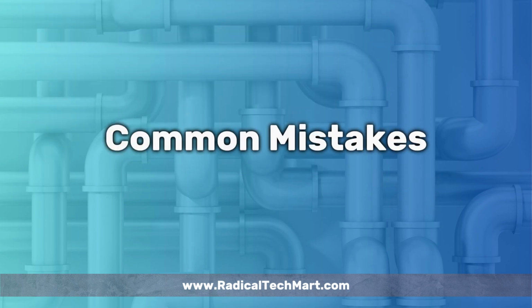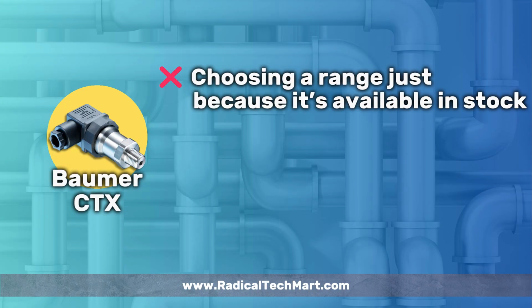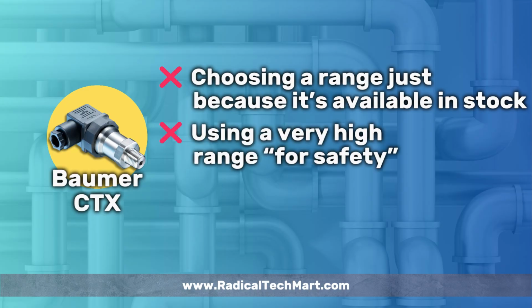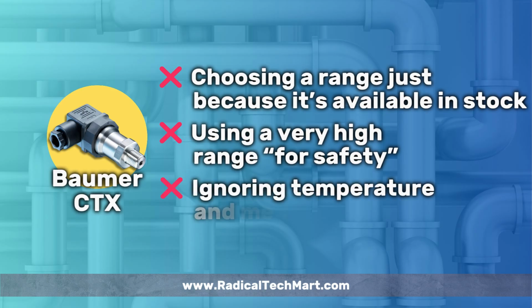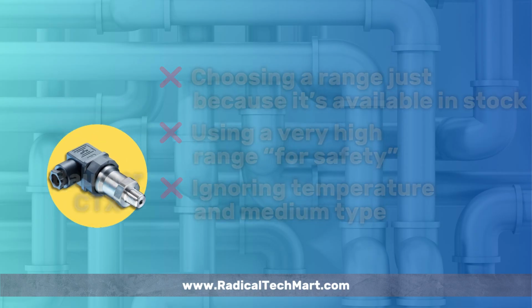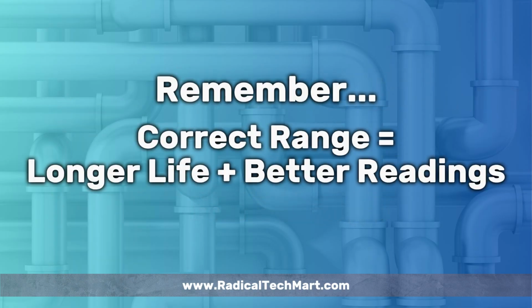Here are some common mistakes engineers make. Choosing a range just because it's available in stock. Always check your system pressure first. Using a very high range for safety. This reduces resolution and accuracy. Ignoring temperature and medium type. For viscous fluids or gases, the response can vary. Remember, correct range is equal to longer life plus better readings.